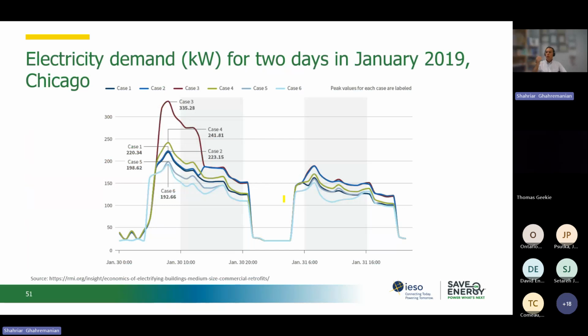This is a typical two days in January operation of different cases at different temperatures. And you see that in some cases, if you have natural gas, for example, then we need to turn on the natural gas backup again, like case 3. But if you have an electric backup system with a rooftop unit with a heat pump, they are more efficient to work during the cold days.